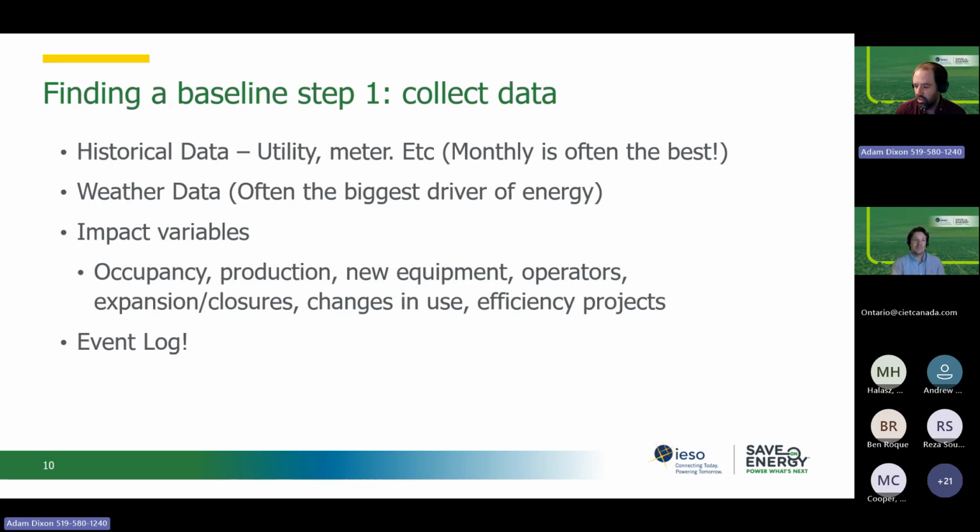So in a school situation, an example here is occupancy. You may not be able to get the attendance of the school. All I use for that is a 1 or a 0. Is it a school day or is it not a school day? And I sum those up for the month, and that gives me my variable to tell you how that's driving the energy.